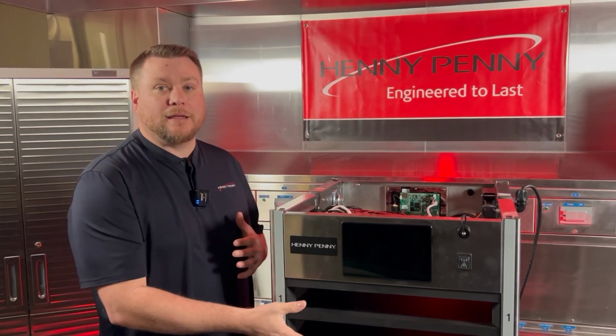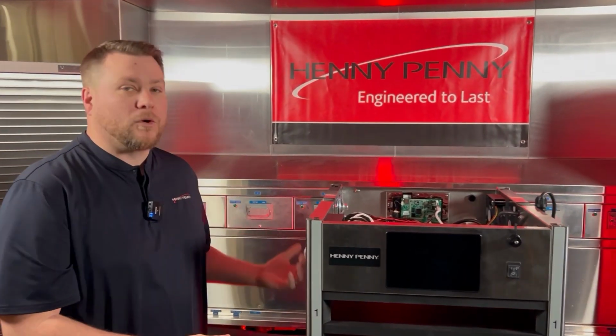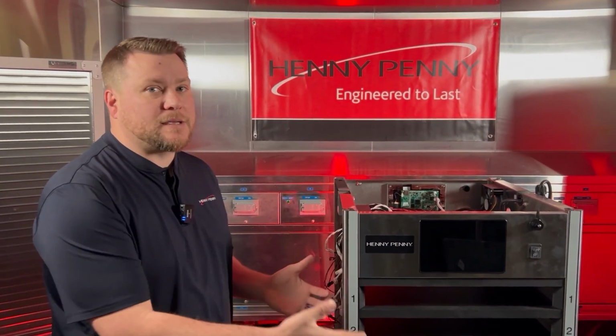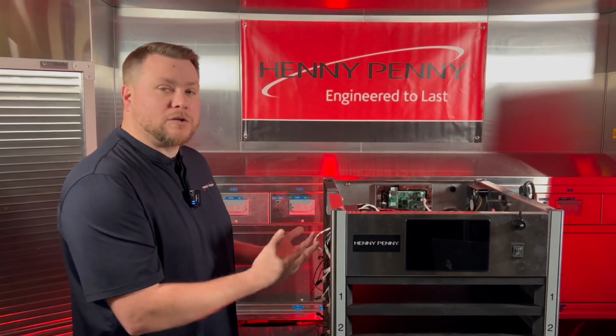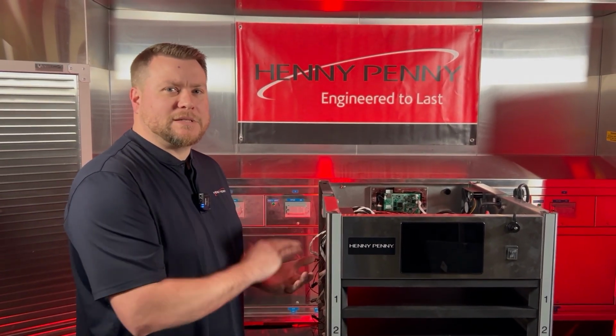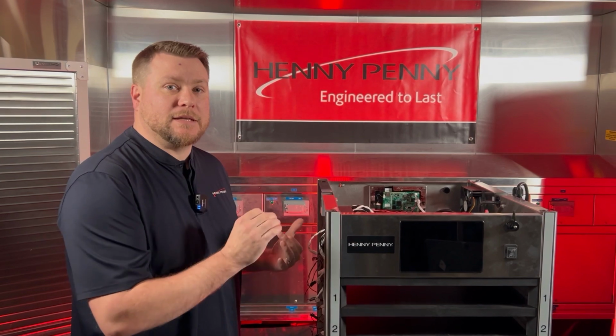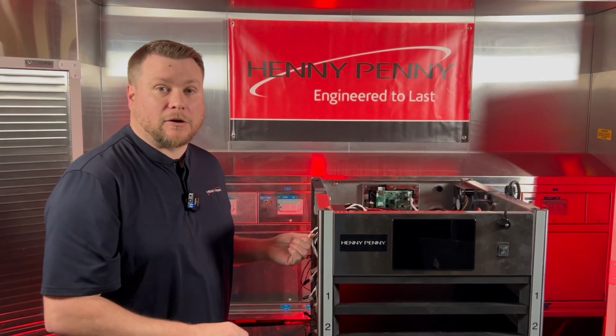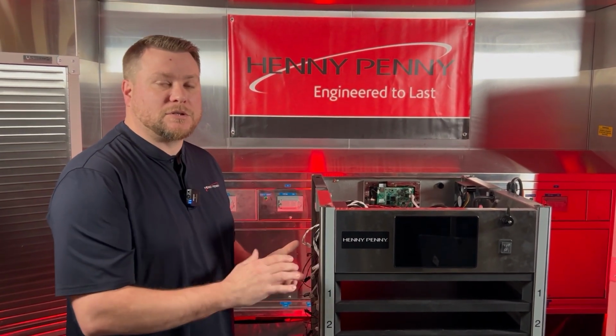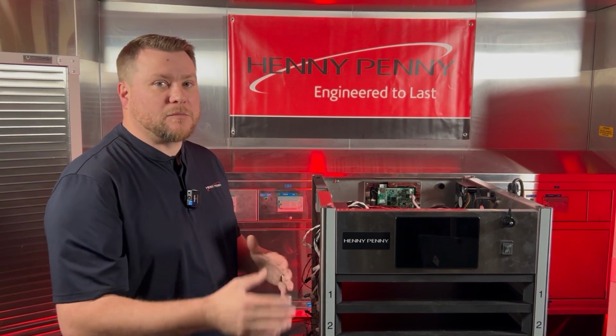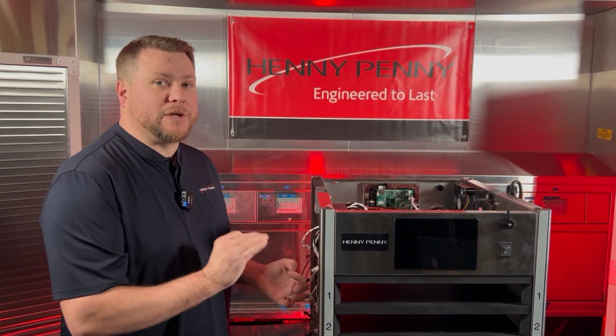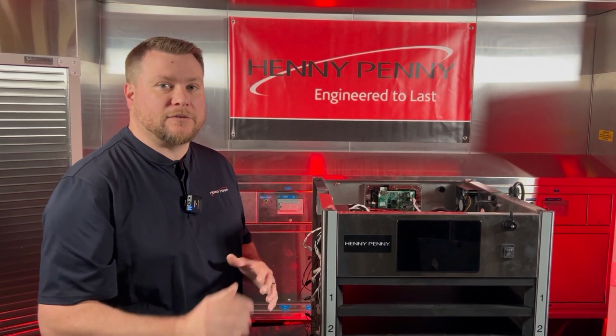Most likely what we're looking at here is either a heater failure potentially, or possibly a temp probe. Now remember, that temp probe's built in there, so what we could do is come over, kind of like what we did on the E-215. We could check our amp draw depending on the voltage that we have supplied. We need to remember those specifications, either 1.29 amps or 1.79 amps.